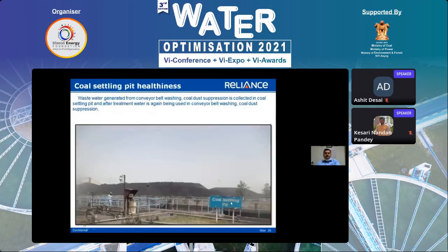This is the coal settling pit. All the coal water is collected in the coal settling pit. Settling is taken care of there, and that water is again used for water sprinkling on the coal at the CHP, so that our fresh water requirement in the CHP has been minimized and nullified. All the coal dust separation is also taken care of from the coal settling pit water.